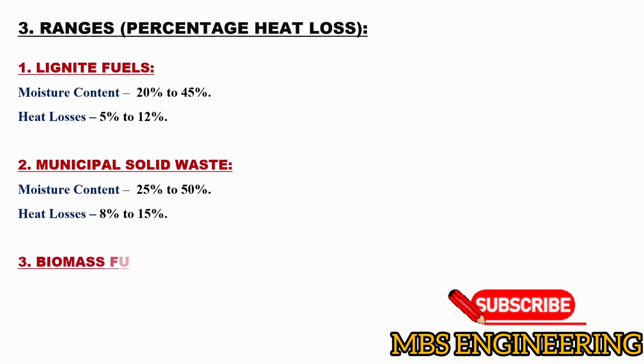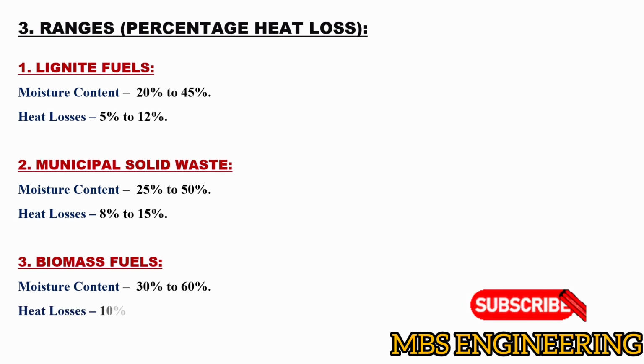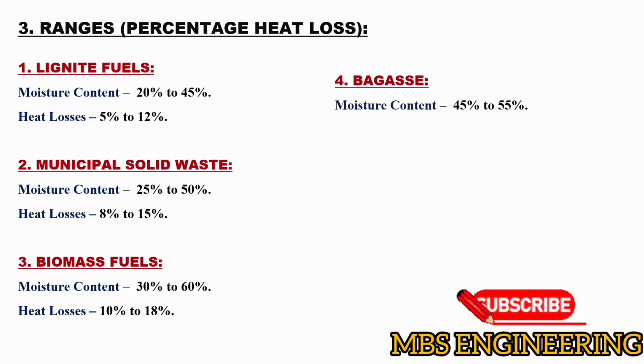Next, in biomass fuels, the moisture content ranges from 30% to 60%, and the heat losses range from 10% to 18%. Next, in bagasse, the moisture content ranges from 45% to 55%, and the heat losses range from 12% to 20%.